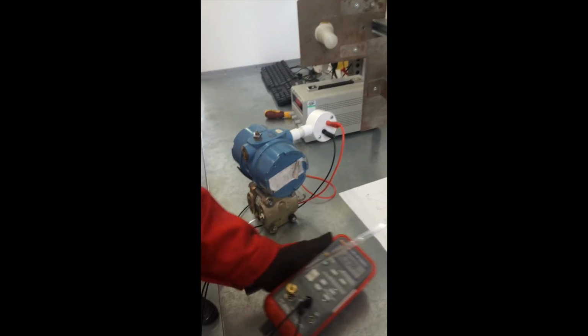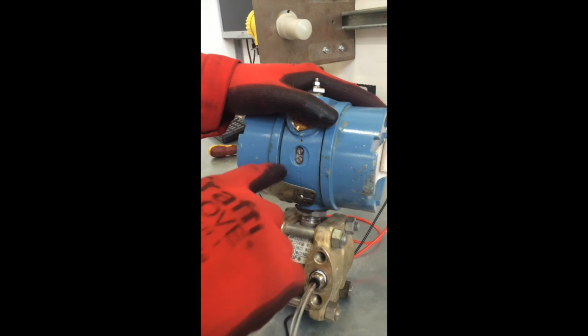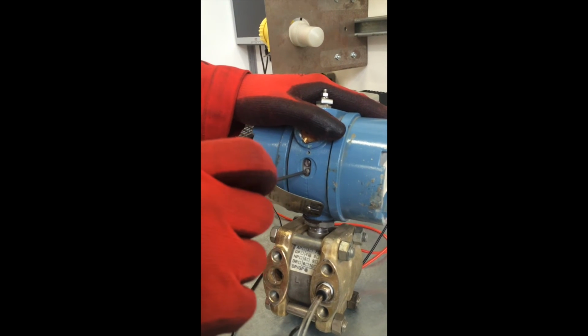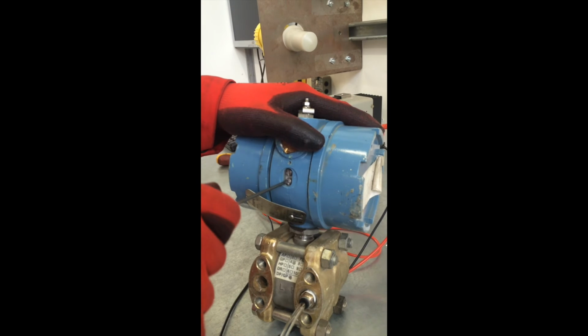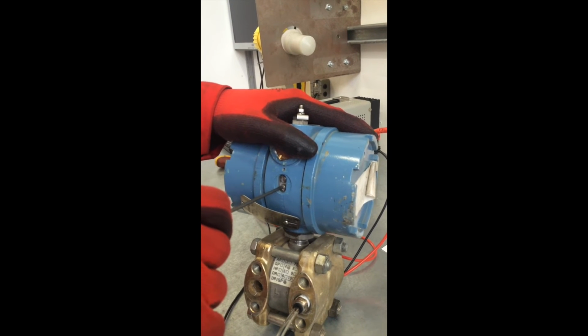So what you do is you go back to your DP cell and use the screw in the bottom, which has a wee R next to it for your range. It's the same as with the 0, but this time you turn it anti-clockwise, and just bring it down to 20.